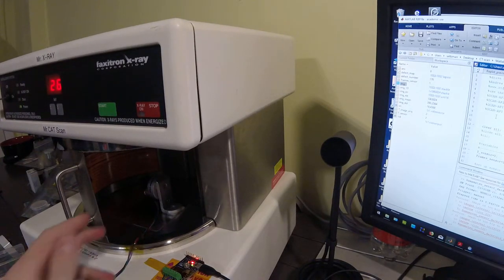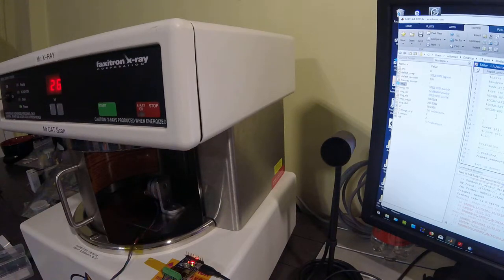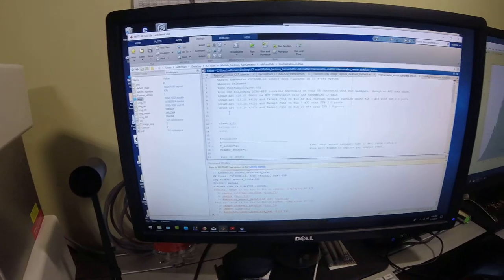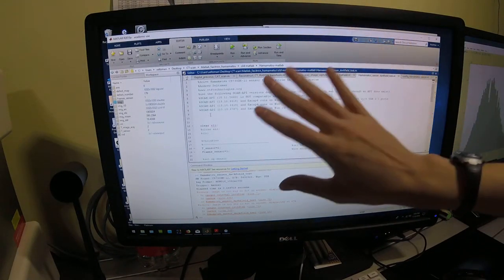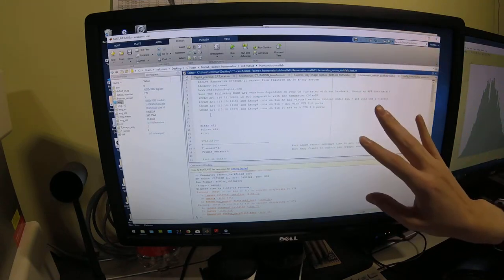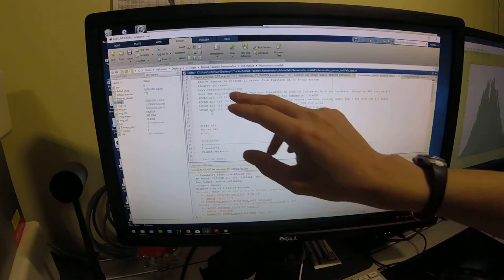And one of the things is that these sensors are covered with a carbon fiber sheet for protection against physical damage. You can actually see some of that carbon fiber sheet as a fixed pattern noise on the X-ray detector. So to calibrate that, there's a MATLAB script that I've written to do that. This MATLAB script runs the sensor through the Hamamatsu DCAM-API interface.